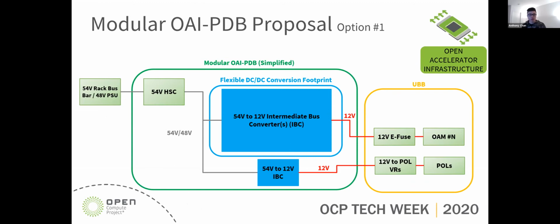At a high level, as we mentioned earlier, we would typically have a 48 volt rack bus bar or a 48 volt PSU from the left. This power would usually go through some sort of hot swap controller solution, and the power would then be further distributed into the converter footprint mentioned here to eventually power the 12 volt OAMs. There will also be some housekeeping power to power any POLs, PCIe switches, or anything else you may need for the rest of the OAI system.